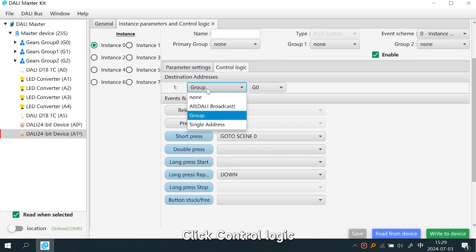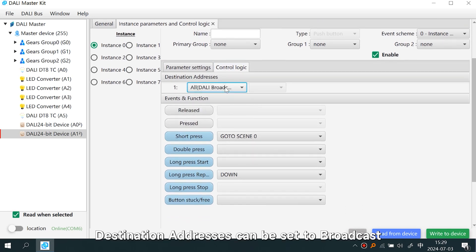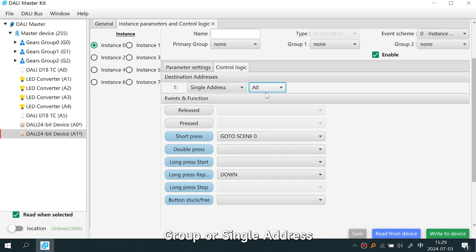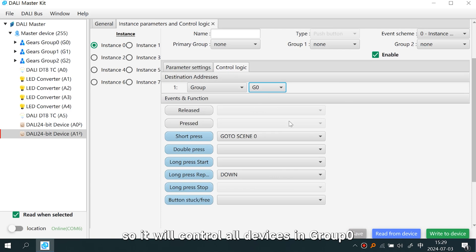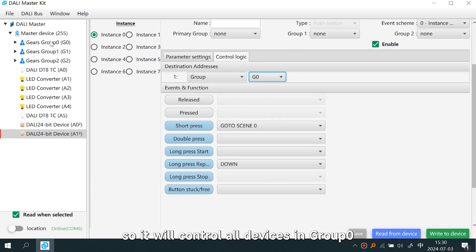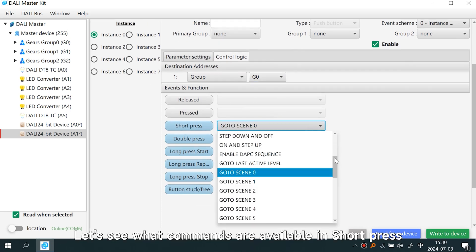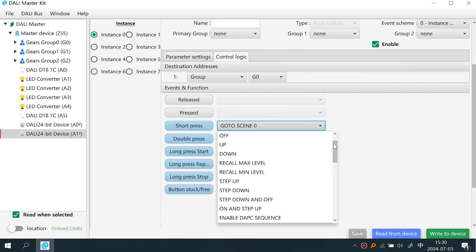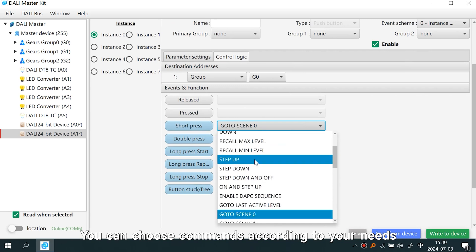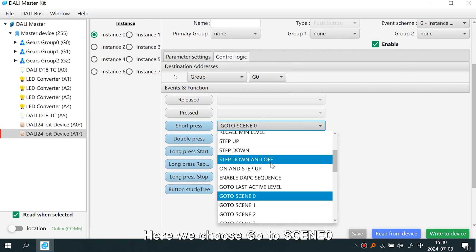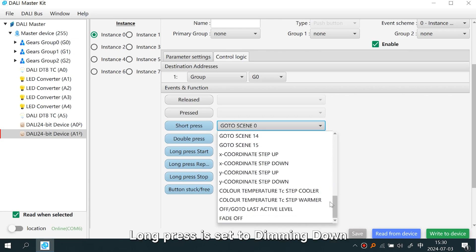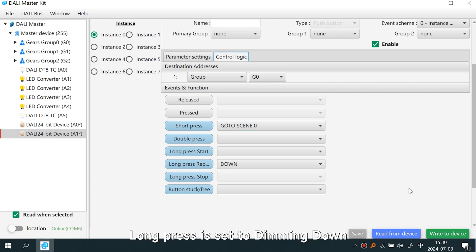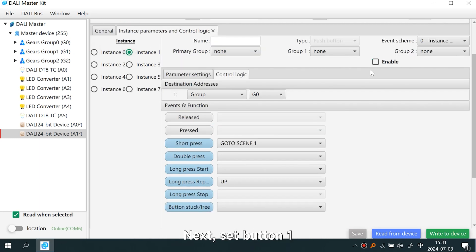Click Control Logic. Destination addresses can be set to broadcast, group, or single address. Let's set it to Group Zero so it will control all devices in that group. In short press, choose the command as needed — here we choose Go To Scene Zero to turn off all the lights. Long press is set to dimming down.